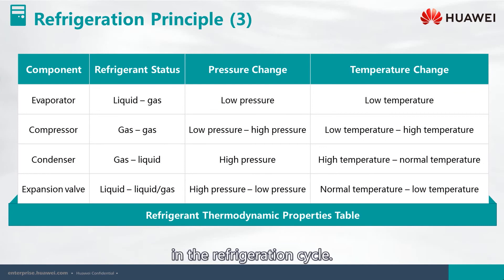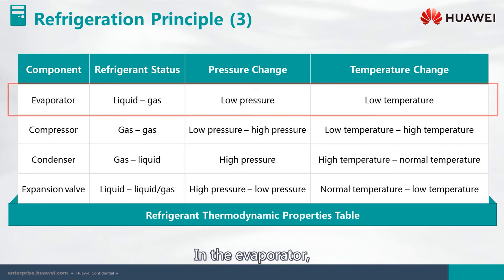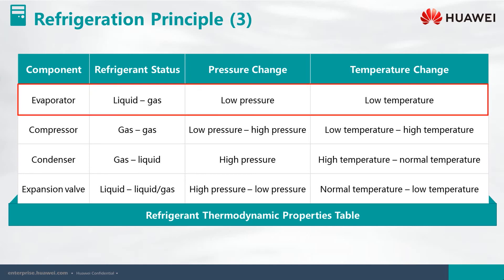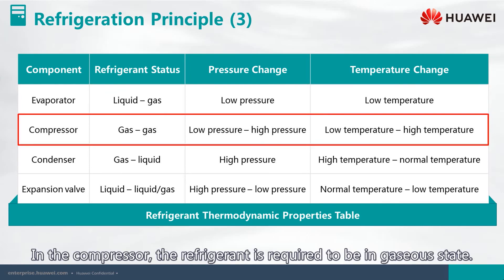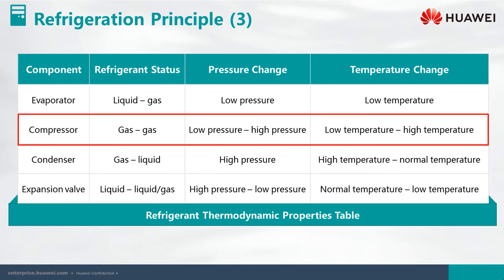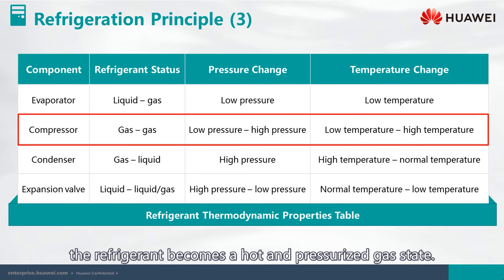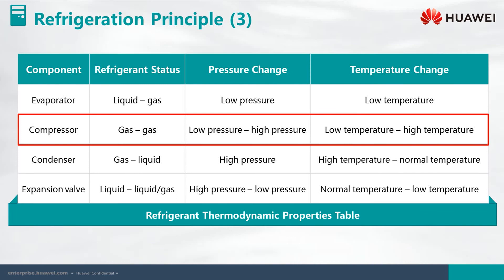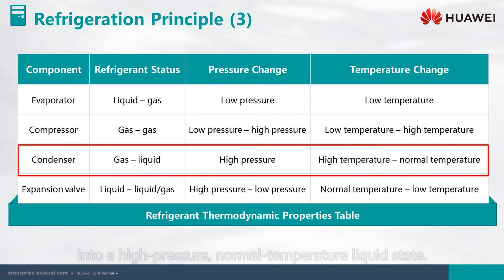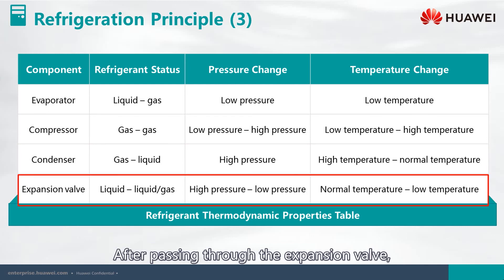The following table lists the thermal state changes in the refrigeration cycle. In the evaporator, the refrigerant is generally a liquid or gas-liquid mixture. In the compressor, the refrigerant is required to be in a gaseous state. At the compressor outlet, the refrigerant becomes a hot and pressurized gas. In the condenser, the refrigerant changes from a hot and pressurized gas into a high pressure normal temperature liquid state. After passing through the expansion valve, the refrigerant becomes a gas-liquid mixture at low temperature and low pressure.